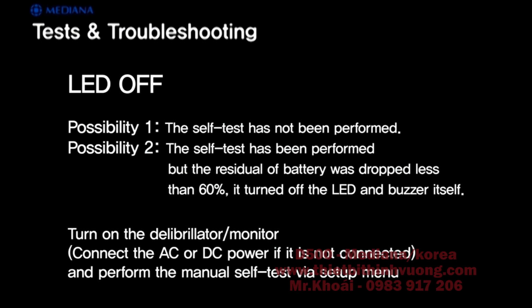If the LED is off, there are two possibilities. Possibility number 1, the self-test has not been performed. Possibility number 2, the self-test has been performed, but the residual of battery dropped below 60%. It turned off the LED and buzzer itself. If this happens, turn on the D500, connect the AC or DC power if it is not connected, and perform the manual self-test via Setup menu.